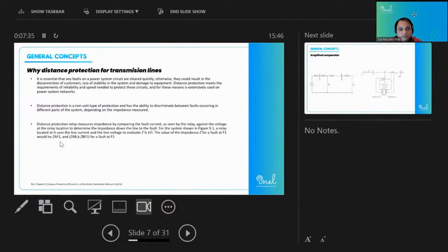And if there is a mal-operation, then a relay should be intelligent to discriminate between abnormal operating conditions and the normal overloading conditions. So these are actually distance protection features which we need to set in the relays. So this is the main reason why we are protecting the transmission lines.